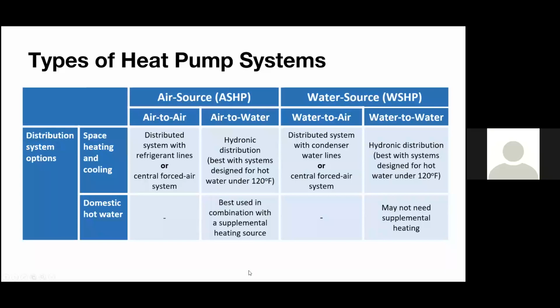So here we're looking again into air source and water source. And you might have heard of air-to-air source heat pumps and air-to-water. So again, air source means it dumps the heat or takes the heat from the air. The other side of the word, air-to-air versus air-to-water, means what are you trying to heat or cool? So an air-to-air heat pump, like your typical mini split, your typical residential air conditioner, it's going to reject heat or take heat from the outdoor air, outdoor ambient, and that's why the first word is air. But then it's also inside the building. It's trying to heat or cool air. So again, it's air to air.